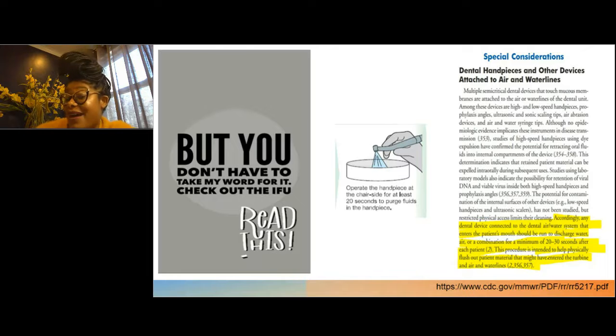But you don't have to take my word for it. If you look at this image right in the middle, you'll see this is a snippet from a dental handpiece IFU. And it says, operate the handpiece at chairside for at least 20 seconds to purge fluids in the handpiece. This IFU actually requires this to be a step that happens in the operatory. They're asking for you to do that. You wouldn't have ever known that it's being requested of you if you've never read the IFU.